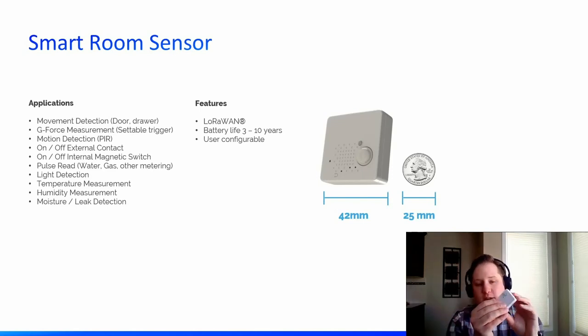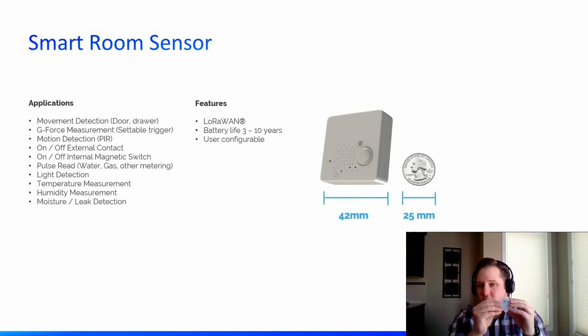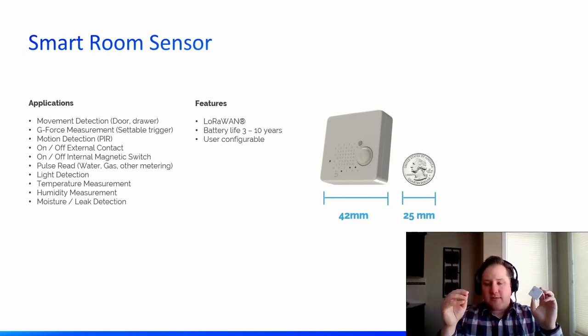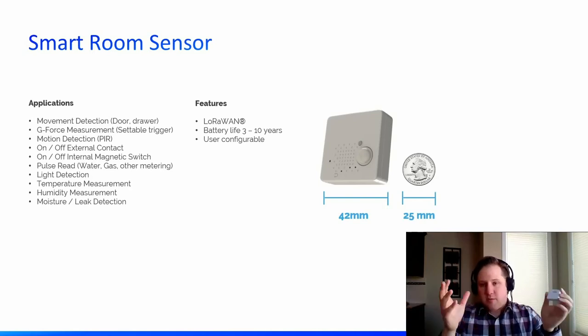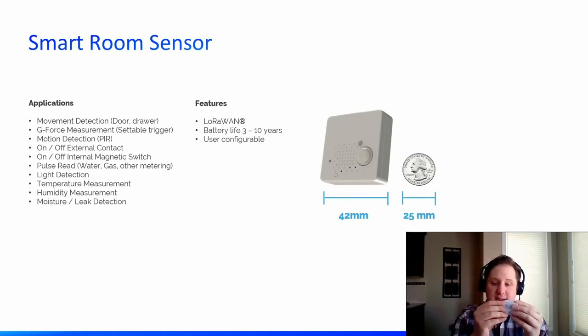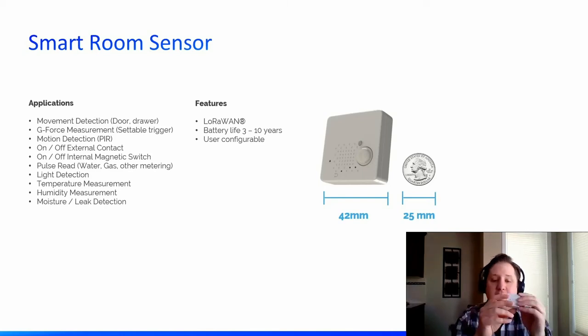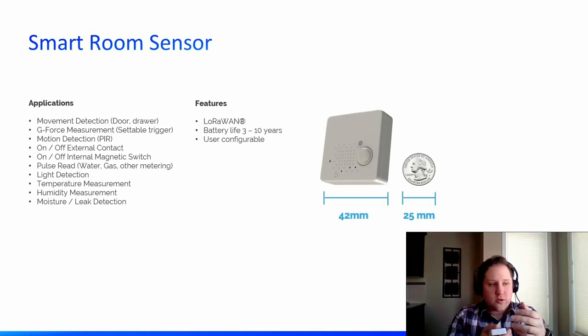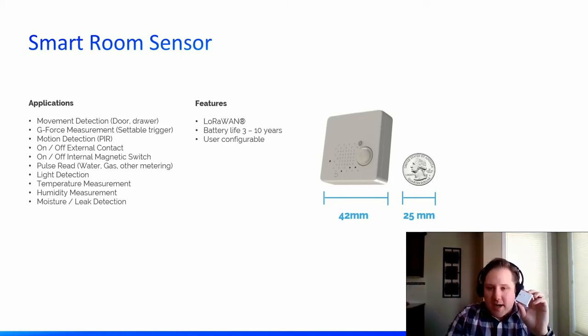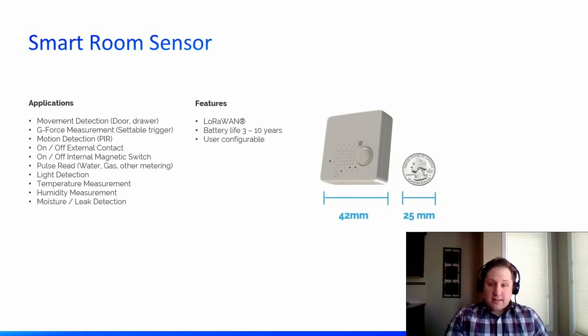We have a variant with passive infrared motion detection to tell you if a room is occupied. We also have various masking options for that motion detection so you can determine — based on the size of the room, whether it's a large boardroom or a narrow hallway — whether those spaces are occupied. We also have a desk presence mask so you could place it underneath a desk and detect if that specific spot is occupied. It has an external magnetic reed switch, so if mounted on a window or door, you can tell if it was opened or closed. We also have a spot for an external connection for probes such as moisture leak detection probes. It also has light detection to tell if the lights are on or off.